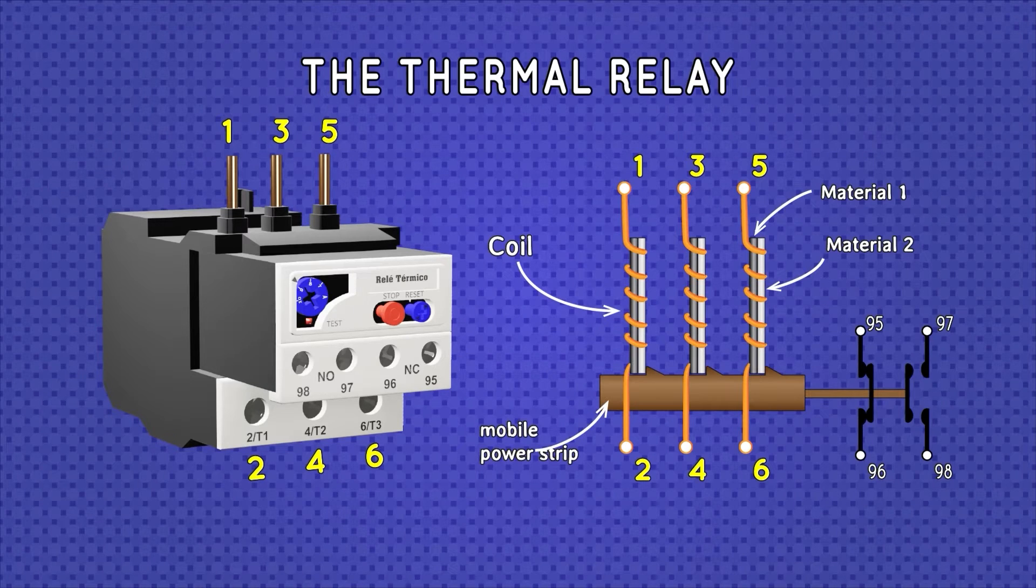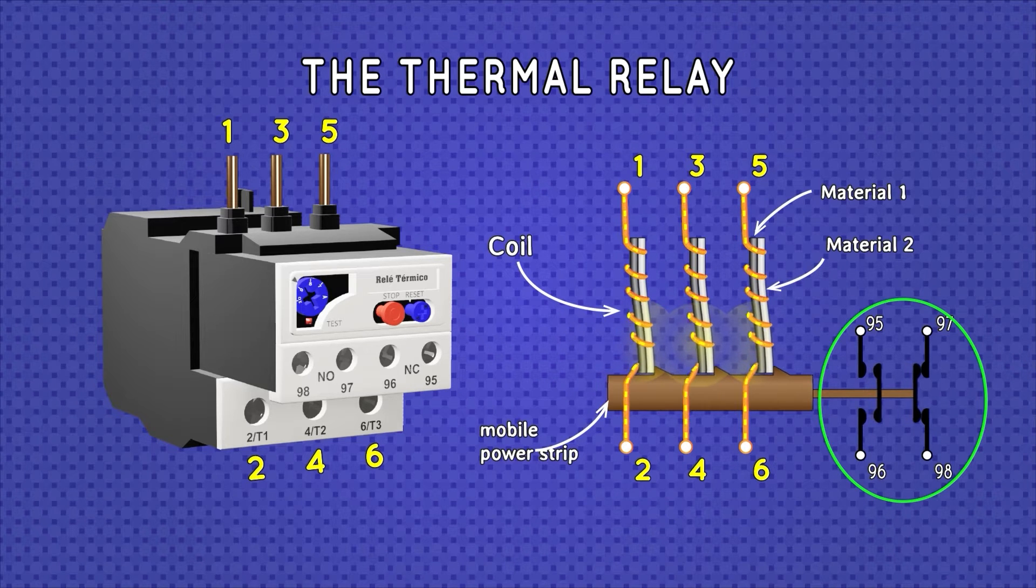Internally, a thermal relay consists of three main bimetals, each of which is constituted by the union of two types of metals with different types of thermal expansion coefficient. In addition, each bimetal has a wire winding which forms a small coil which, when current circulates, the bimetals deform and push the moving strip.